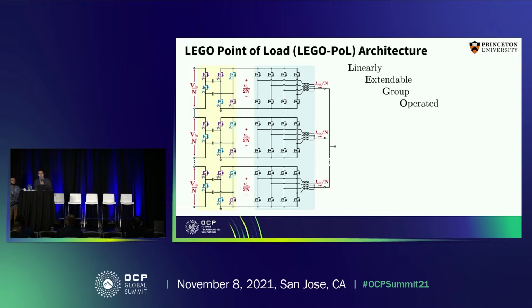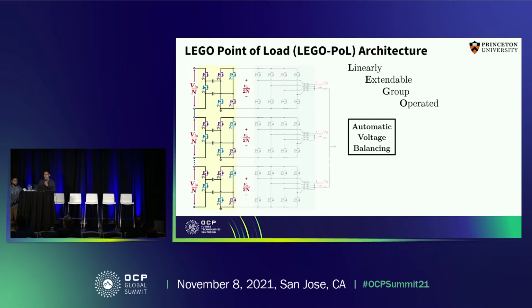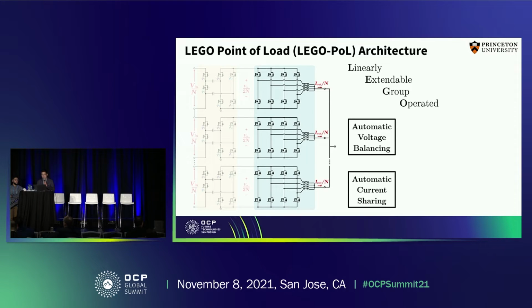One very important function to develop a very high output current converter is that we need to get automatic voltage and current balancing. If the voltages and currents are not balanced, you need to use sophisticated active control, and then this building block approach doesn't make sense, or it becomes very expensive. A major advantage of this architecture is that it automatically balances the input voltages and shares the output current evenly through each building block without any active control.